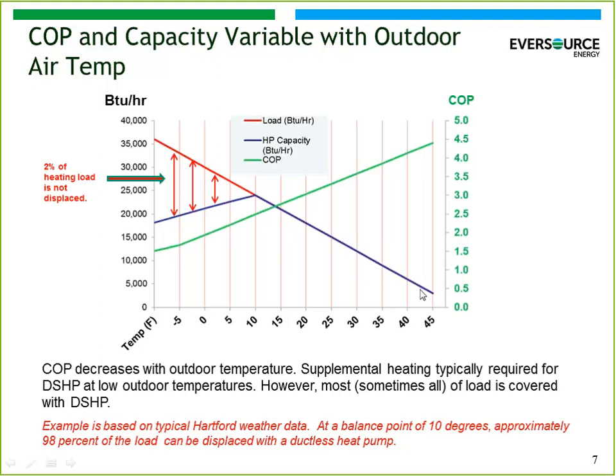If we look at a typical ductless heat pump, ductless heat pumps have the ability to basically match the load. So if you start at 45 degrees, the ductless heat pump's going to be fine. As you move up the scale, it's still going to be able to serve the load, and somewhere, and this number varies, but let's just say somewhere around 10 degrees, the ductless heat pump isn't going to be able to maintain or satisfy the thermostat in the home. And we saw on the previous slide that they work much better than previous generation heat pumps, but their performance is still going to start to decline a little bit as the temperature gets close to zero or below zero.